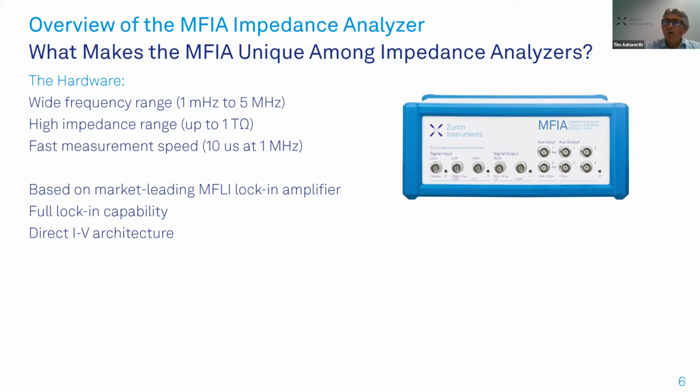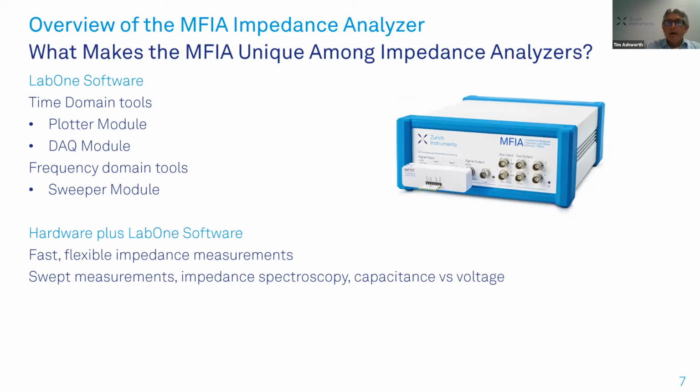And a word on the architecture. In contrast to some other impedance analyzers, we don't use an auto balance bridge. We make a direct IV measurement, and this really allows us the ability to measure quickly. So that was a little bit about the hardware.